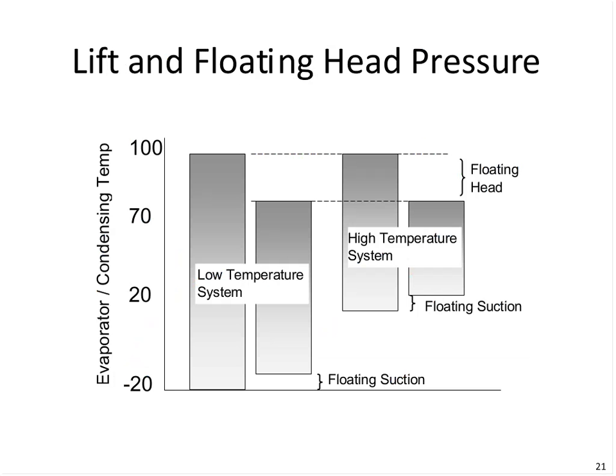Okay, now let's take a look at the floating suction. Notice there's not as much opportunity here. Of course, Mother Nature outside is fluctuating a lot through the seasons and through the day. Over here, we have a requirement to maintain the product, but we don't always have to be at the coldest temperature. So here we're employing a few degrees of floating suction. Of course, a few degrees is several percent of savings, so we can achieve this and desire to have the controls able to do that.